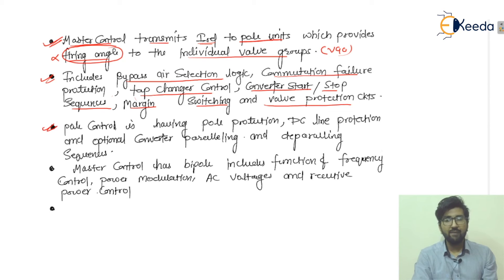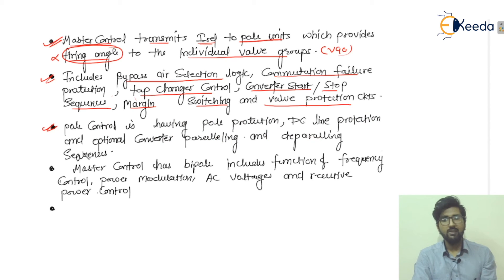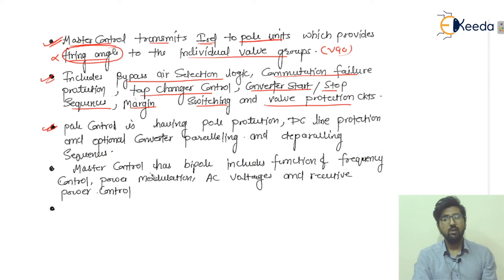The pole control includes pole protection, DC line protection, and optional converter paralleling and deparalleling sequences. The master control at the bipole level includes functions such as frequency control, power modulation, AC voltage control, and reactive power control.